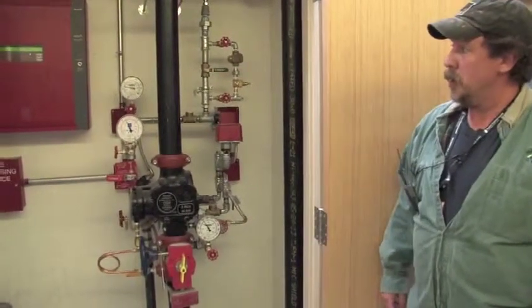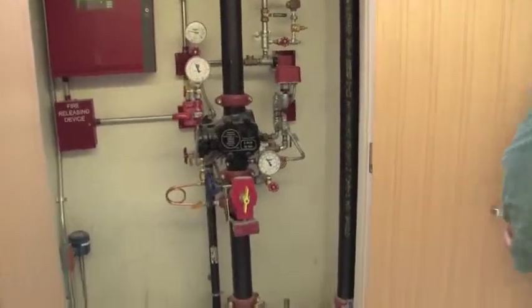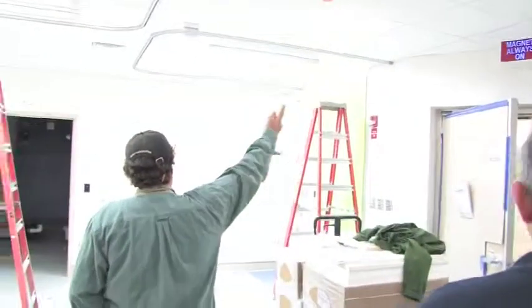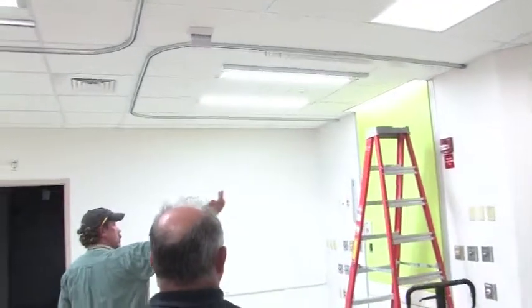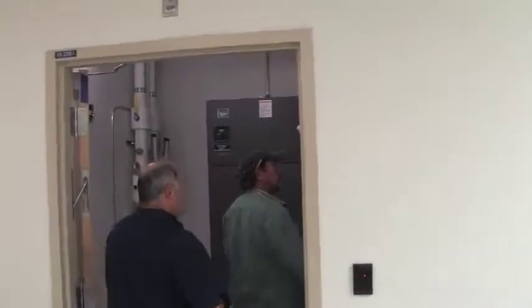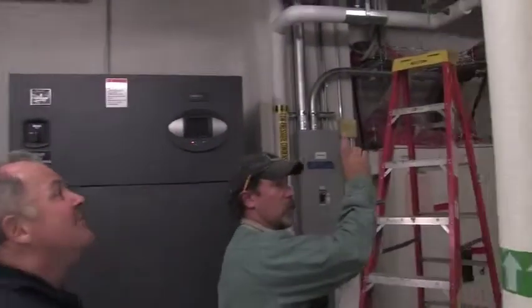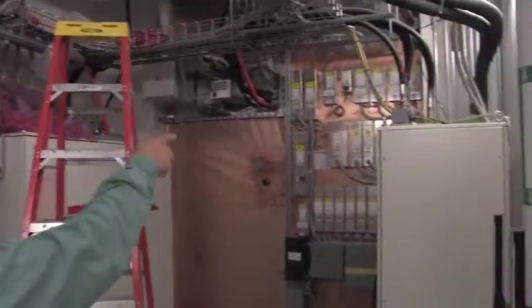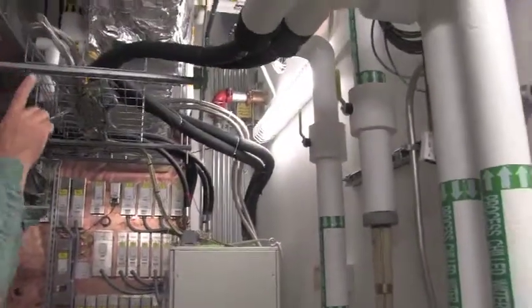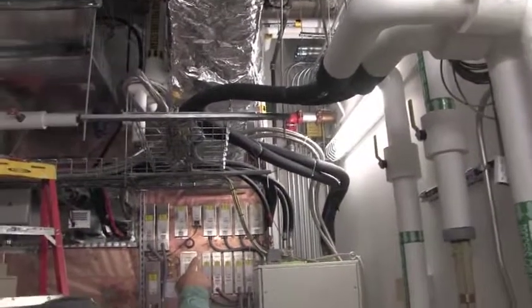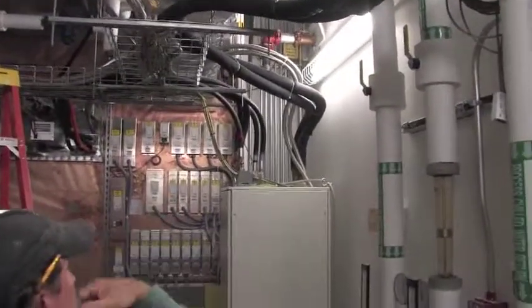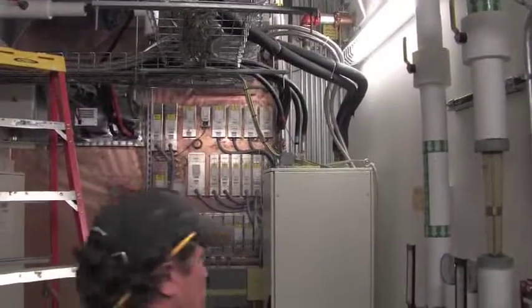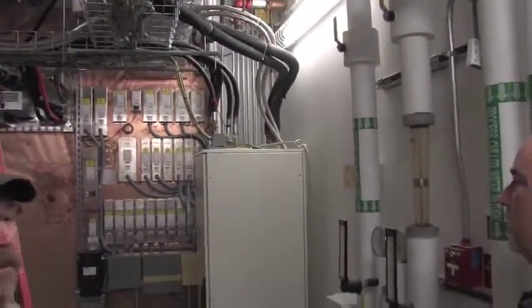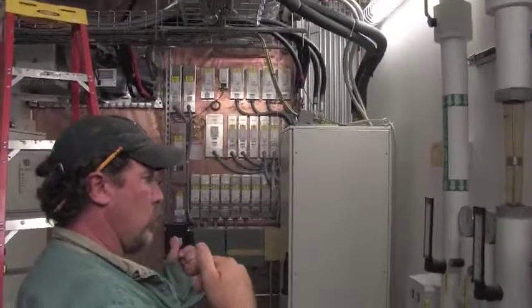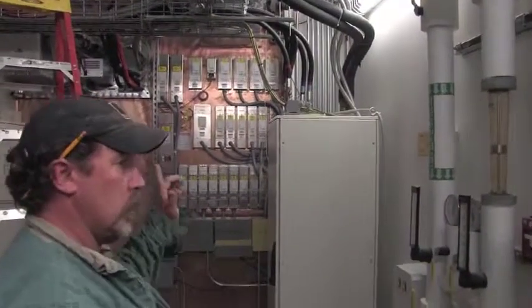When I show you the MRI and what this is heading to, right through these doors over here, guys. The pipe runs through over here, runs into the MRI little mechanical room here. And it feeds through there. These heads here, don't let these sprinkler heads fool you. These are coming off of the MRI piping. Just this room here. Everything out there is off of your regular wet system. The mechanical rooms are fed off the pre-action system, as well as inside there.